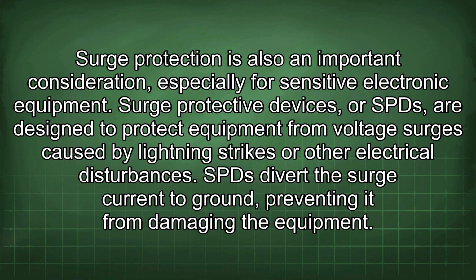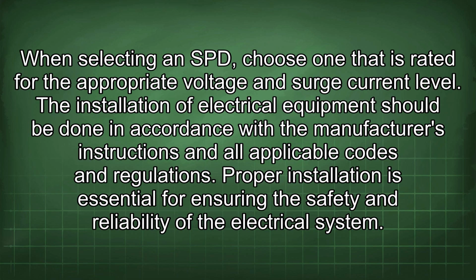Surge protection is also an important consideration, especially for sensitive electronic equipment. Surge protective devices, or SPDs, are designed to protect equipment from voltage surges caused by lightning strikes or other electrical disturbances. SPDs divert the surge current to ground, preventing it from damaging the equipment. When selecting an SPD, choose one that is rated for the appropriate voltage and surge current level.